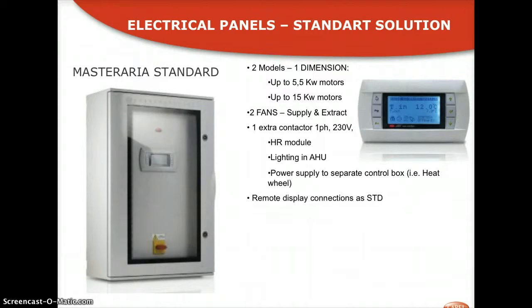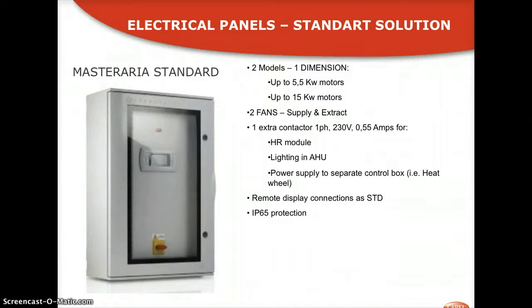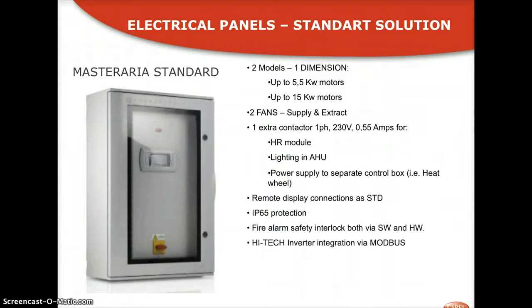There is a splitter which allows you to connect a remote display if you want to. The box is entirely weatherproof, it's IP65, so is suitable for an outdoor installation, and is also fitted with a relay which can cut completely power to the contactors in case of a fire alarm. This is an additional safety to what is already equipped by the digital inputs fire alarm to the controller, which will do the same thing but via software.